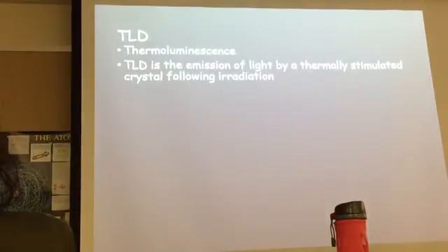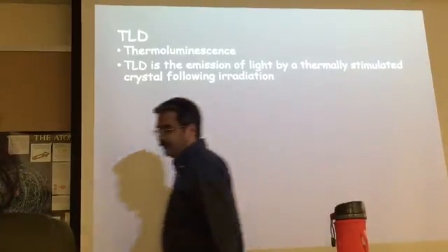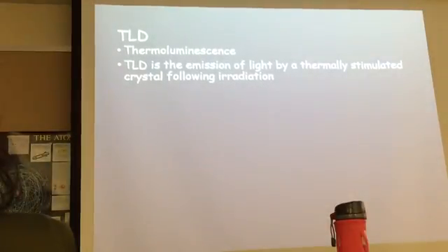Does it make any sounds? Does it emit light when you get exposed to radiation? No, you don't know when you get exposed, but you get a reading. That's what TLDs do. TLD stands for thermoluminescent dosimeter. The TLD is the emission of light by a thermally stimulated crystal following irradiation.